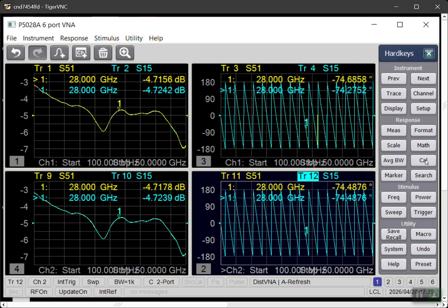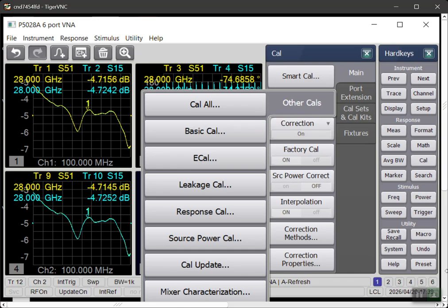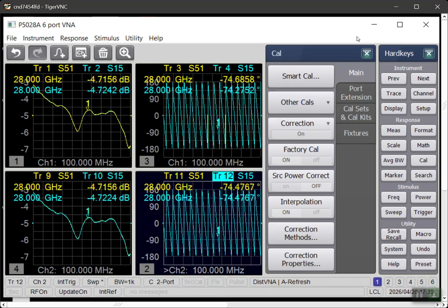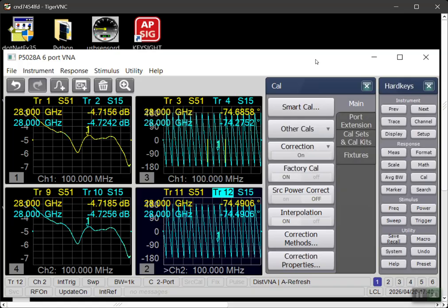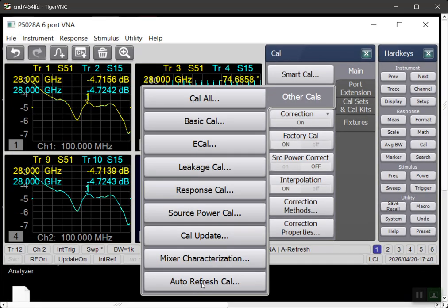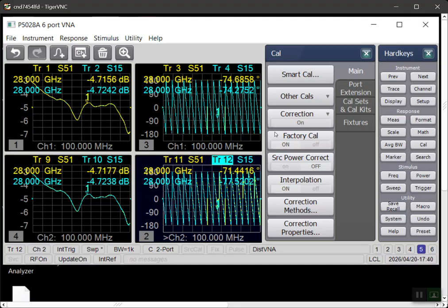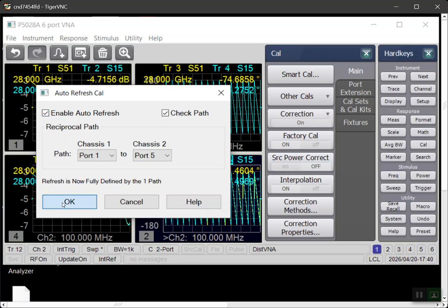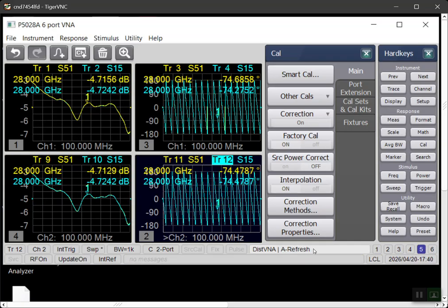If I turn off cal auto refresh, let me make this smaller so I don't have to keep scrolling. Cal auto refresh, if I turn it off, you can see it's the measurement with some level of drift. But you can just leave this auto refresh cal on in the background. It puts the annotation, it maybe slows the measurement down, but very little. So that's how it does the correction. And oh, we're in distributed VNA mode here.